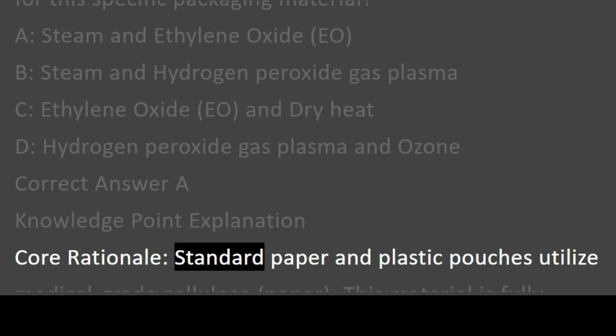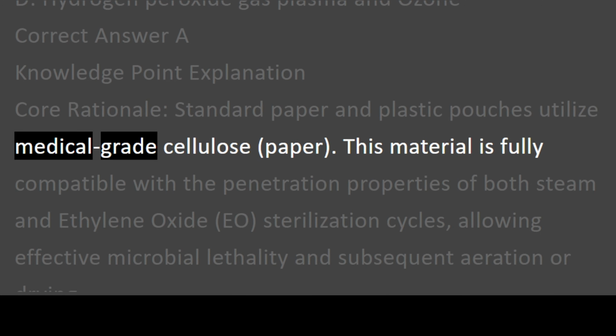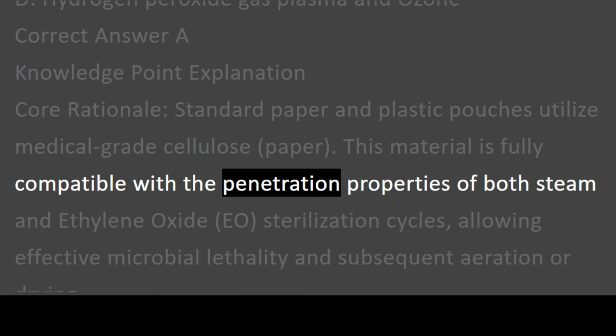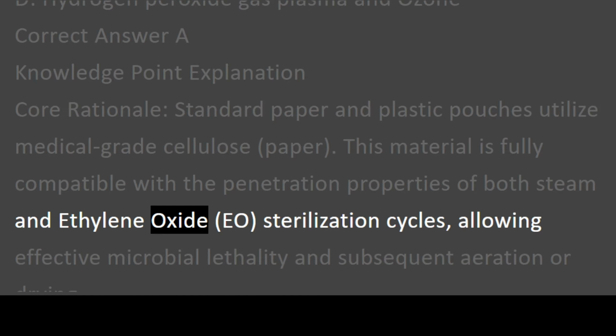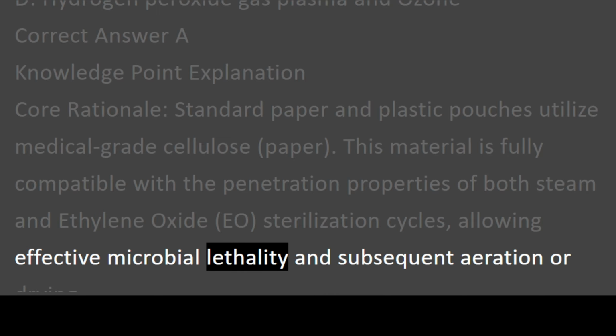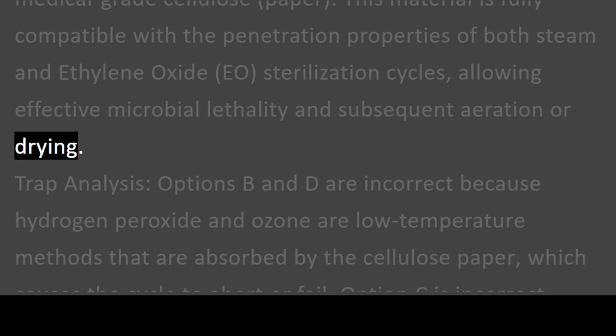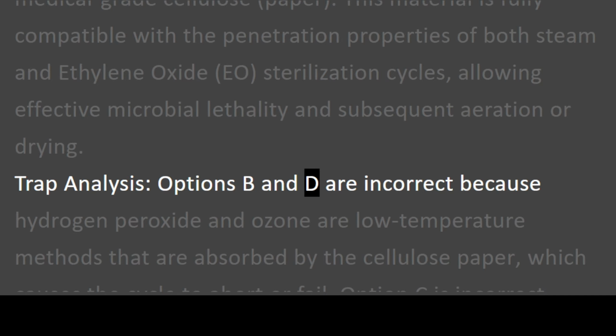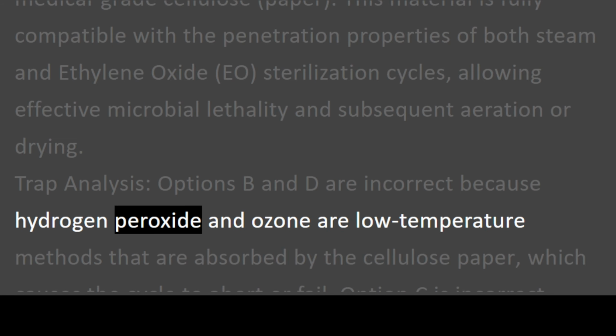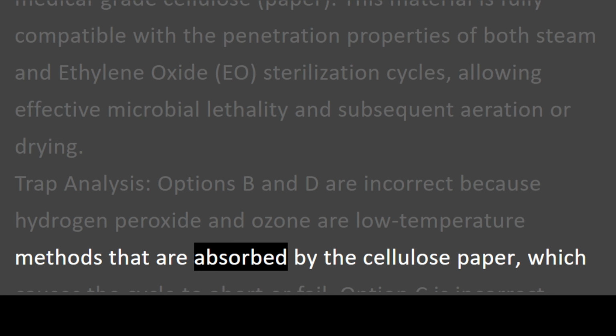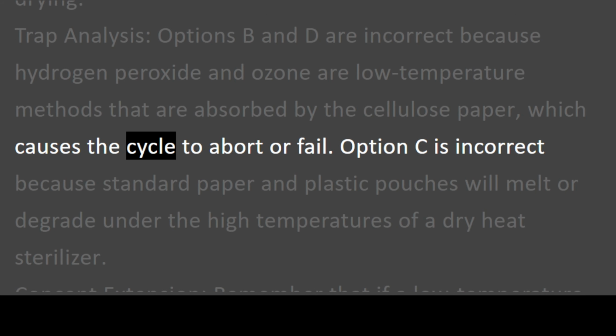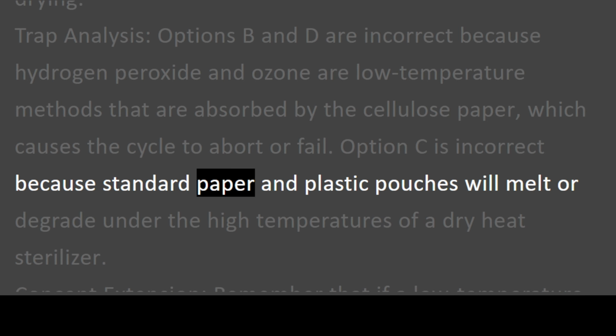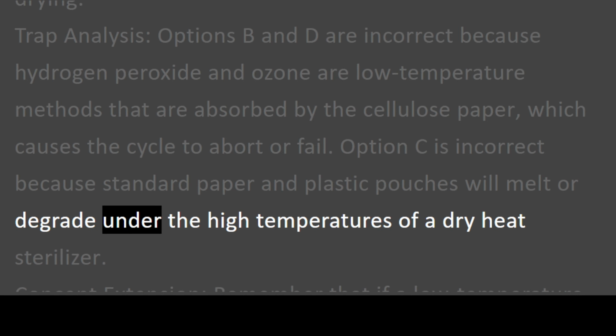Core rationale. Standard paper and plastic pouches utilize medical-grade cellulose paper. This material is fully compatible with the penetration properties of both steam and ethylene oxide, EO, sterilization cycles, allowing effective microbial lethality and subsequent aeration or drying. Trap analysis. Options B and D are incorrect because hydrogen peroxide and ozone are low-temperature methods that are absorbed by the cellulose paper, which causes the cycle to abort or fail.